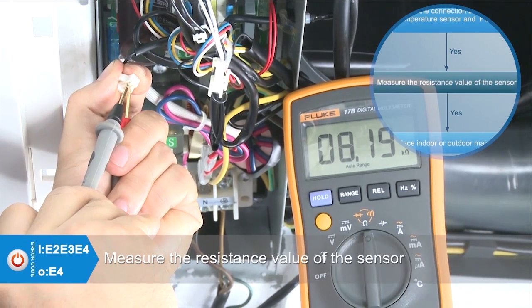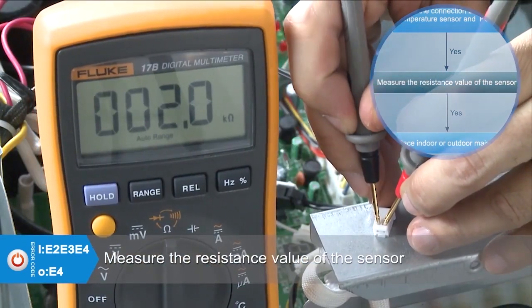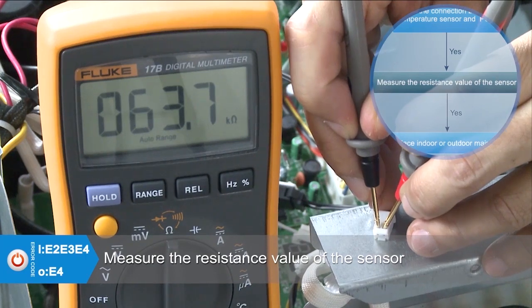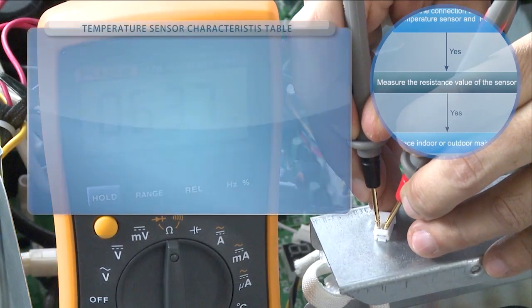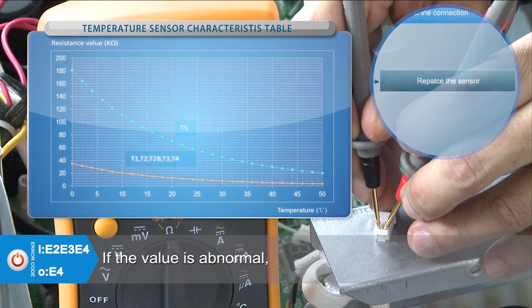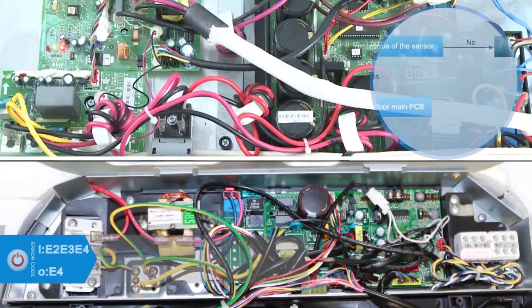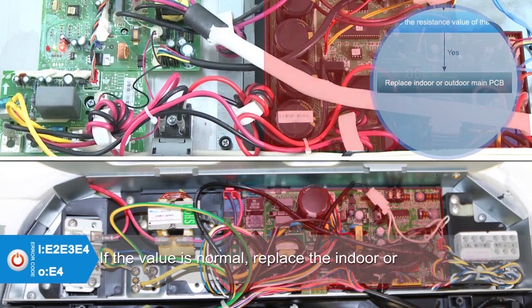After checking the connection, measure the resistance value of the sensor. Check the resistance value according to the characteristic table. If the value is abnormal, replace the sensor. If the value is normal, replace the main PCB.